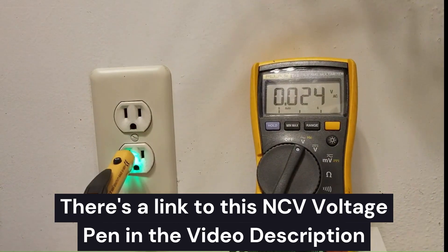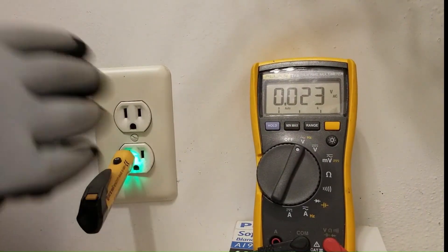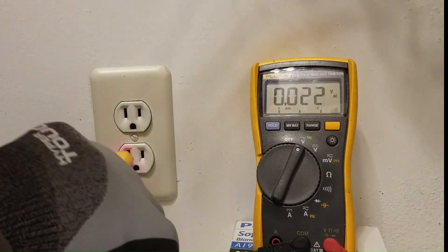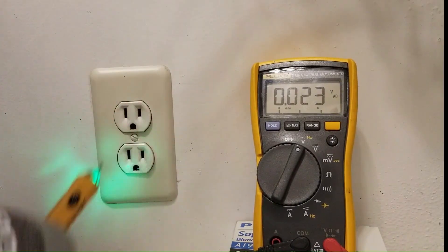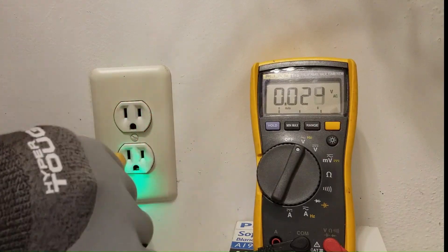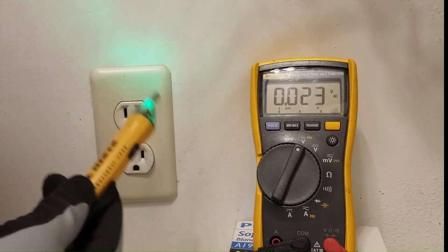So the voltage pen is indicating that neutral is getting pulled up to 120 volts when we plug this in. So that's a really good way a voltage pen can tell you if you have a loose upstream neutral with respect to this outlet that is causing this outlet to fail under load.